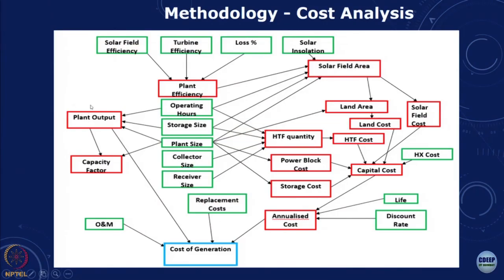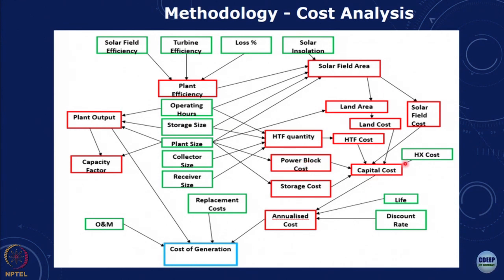Looking at all the components of a solar thermal plant, we estimate the different cost components: the solar field, the turbine, and the solar insolation. For a given location, we know the solar insolation, and from that we can estimate the solar field area, solar field cost, land area, land cost, and heat transfer fluid cost. We also get the power block capital cost from the turbine, generator, and heat exchangers. From this total capital cost, we can annualize it based on a discount rate and calculate the replacement cost and capacity factor.